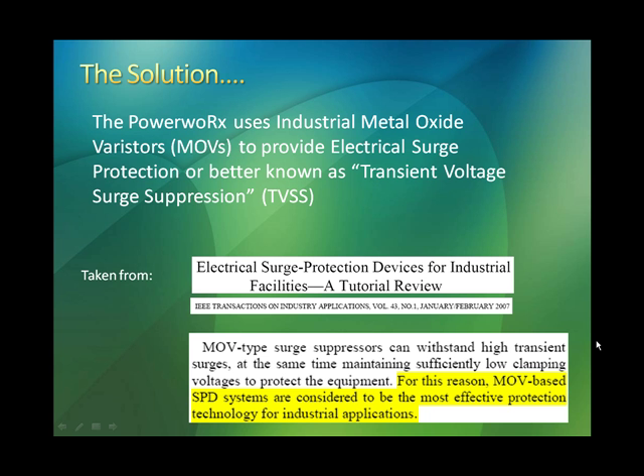Taking just one sentence out of that, I want you to make note. It says, for this reason, MOV, or metal oxide varistor-based SPD, surge protection devices, systems are considered to be the most effective protection technology for industrial applications. And let me tell you, if it's the most effective technology for industrial, you couldn't get anything better to use for commercial or residential. MOVs are the best technology available today, and the PowerWorx has industrial rated MOVs within the product.